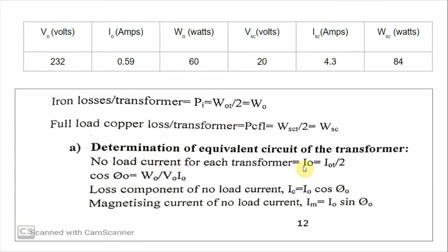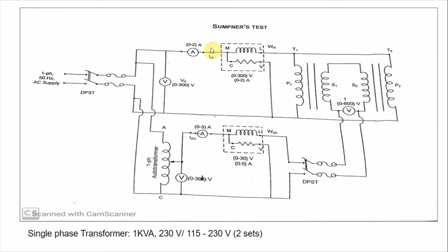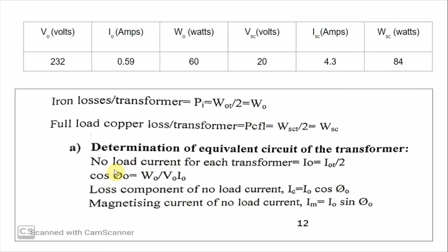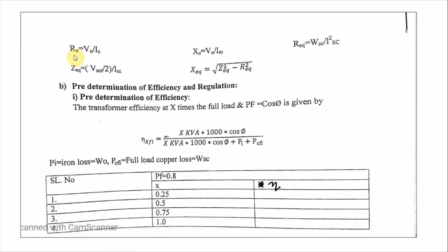Now the no load current IOT in this circuit is divided into two primaries, so the no load current for each transformer is IOT divided by 2. Using this we calculate the no load power factor, which can be used to calculate IC and IM, the loss component and the magnetizing component of the no load current, using this expression. Once we have IC and IM, we can calculate the magnetizing circuit shunt parameters R0 and X0. These two are calculated using the OC test.